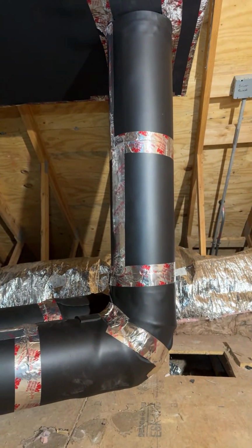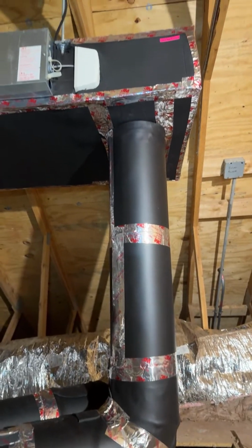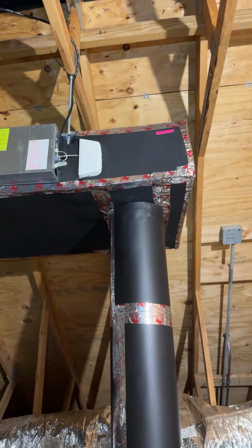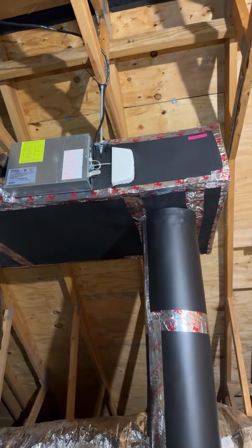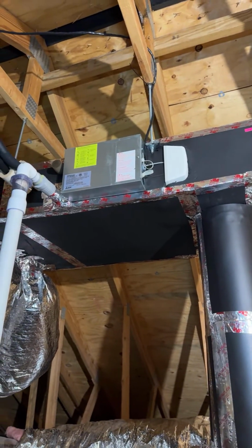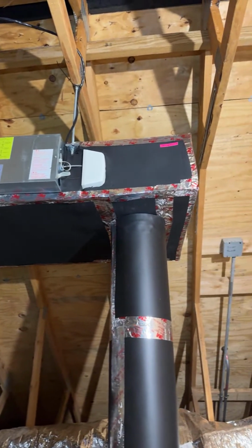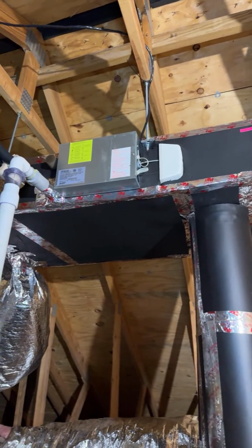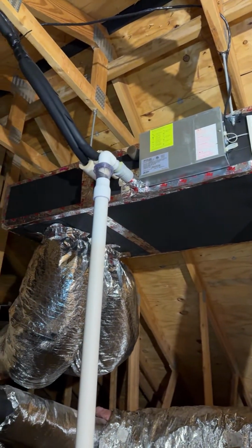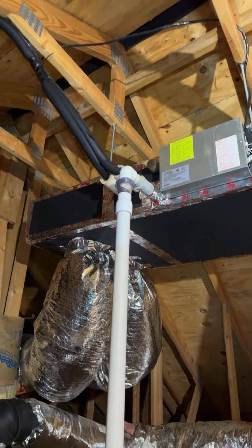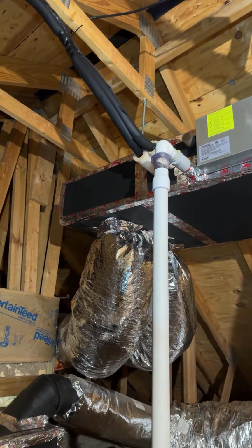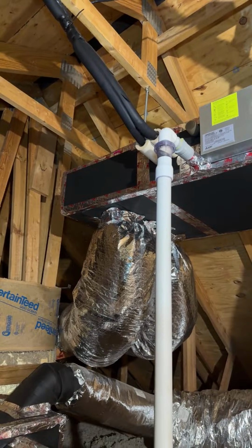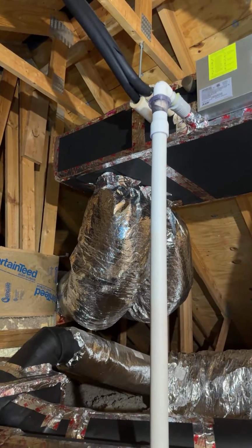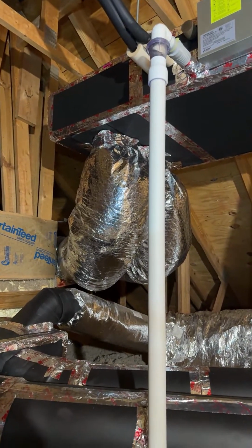And so what did we do? Well, we wrapped it in neoprene. So this is a Mitsubishi mini split ducted system. That top section is the body of the unit. The return air is coming in from there. It's conditioned by the middle section. That's our condensate drain coming out, as well as our refrigerant lines at the top. And then we have the supply going into two bedrooms that are about, on either side.